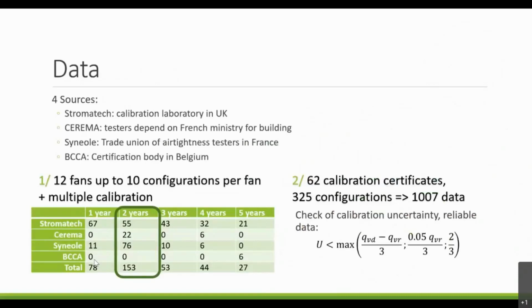So we had 4 sources of data. One is Stromatech, which is a calibration laboratory in the UK. The second one is Cerema, which is a tester depending on the French Ministry for buildings. So they are not using their fan very often. It's more for research projects, so it's a few times a year and not every day. We have also data from Syneole, which is a trade union of airtightness testers in France, so there are fans that are really used every day. And we have also data from BCCA, which is a certification body in Belgium.